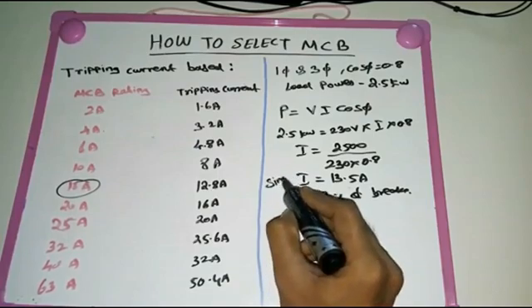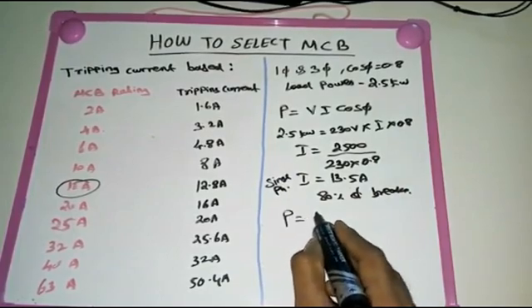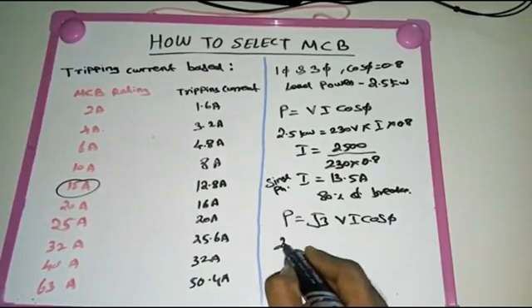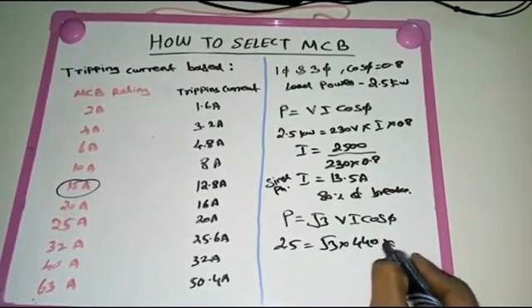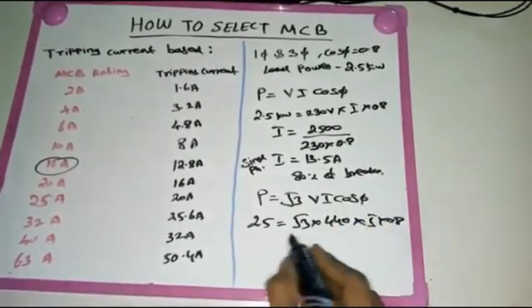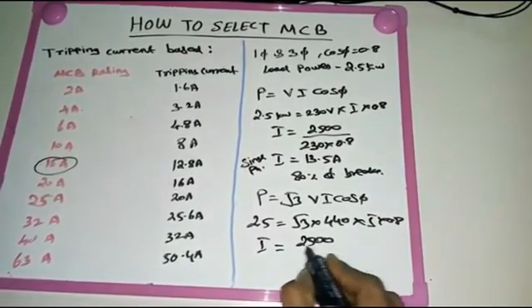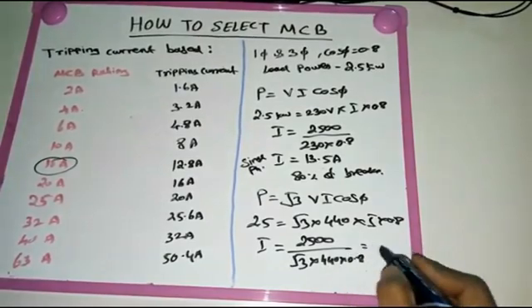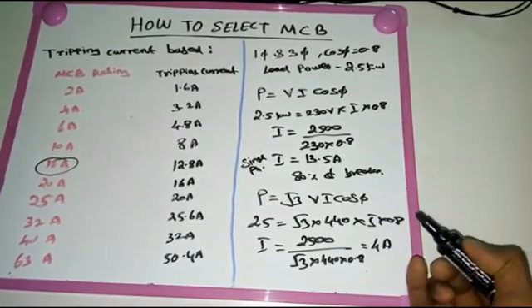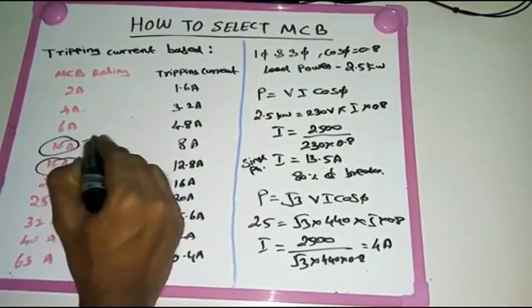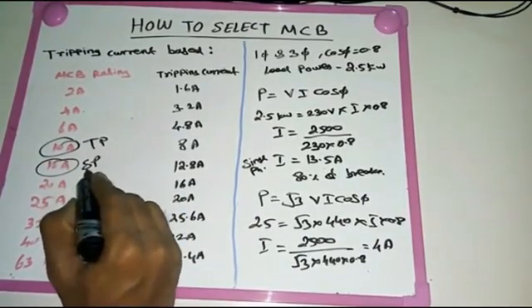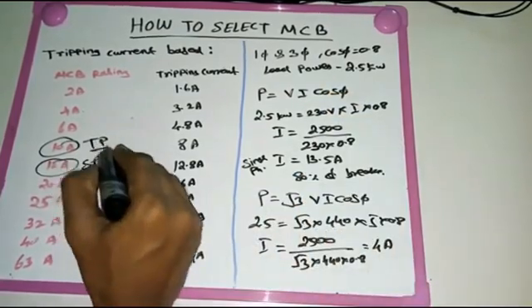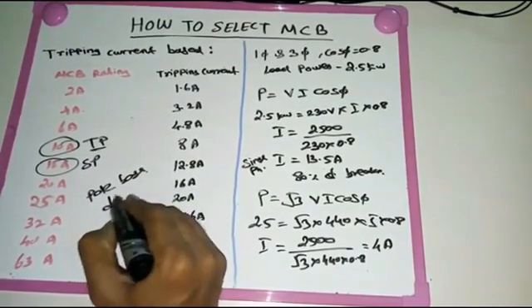For three phase with the same 2.5 kilowatt load, we use P = √3 × V × I × cos φ with voltage = 440V and power factor = 0.8. The calculated current comes to approximately 4 ampere. Since triple pole (TP) MCBs are not available below 10 ampere in small ranges, we select a 10 ampere TP MCB.